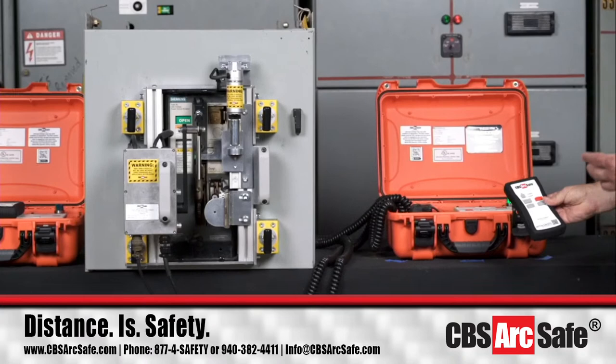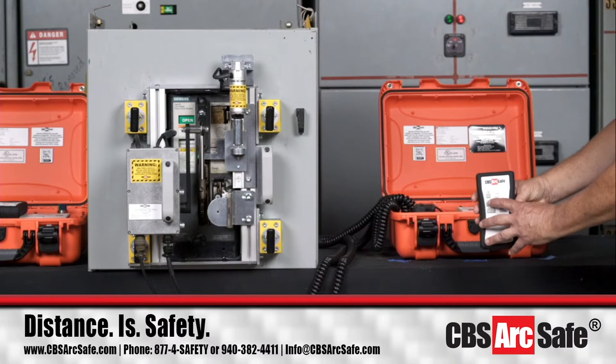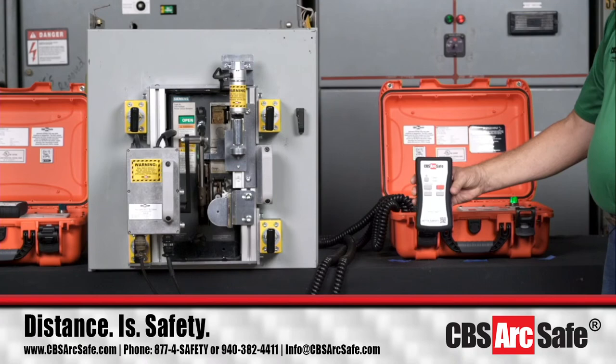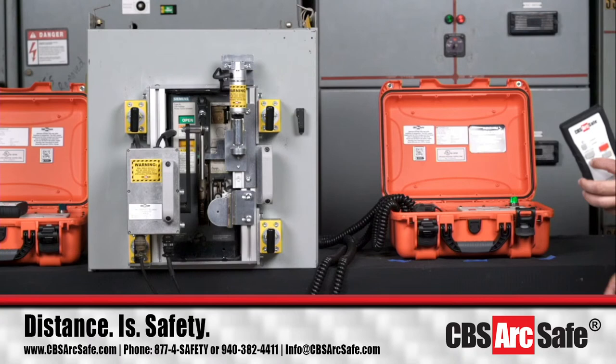So now, remember, we had to label things because of older breakers like a GE AK or a K-Line, where when we pull it down on one stroke, it may charge and close. So the nomenclature is charge close, and I just push this once. I don't have to hold it down or anything. It's going to now tell it to operate. Okay, so we've got our spring charged in here, and now we're going to hit our close, and you're going to hold the button down until you hear the breaker close, and then you're going to release it.